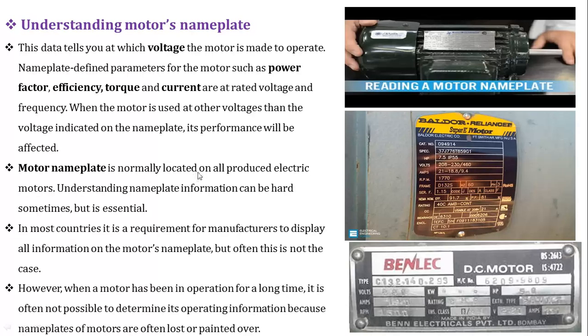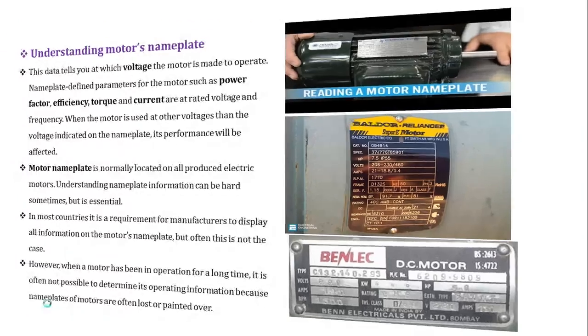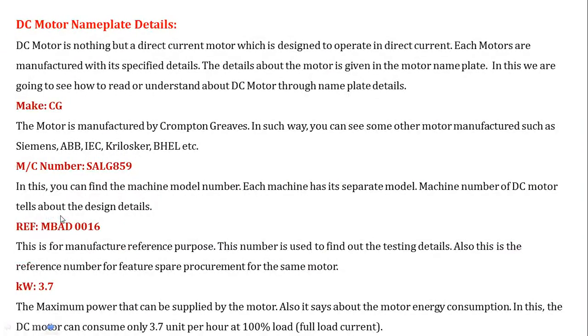The motor nameplate is normally located on all produced electrical motors. Understanding the nameplate's information can be hard sometimes, but it is essential. In most countries, it is required for the manufacturer to display all the information on the motor's nameplate, but often this does not happen. Also, when the motor has been in operation for a long time, it is often not possible to determine its operating information because the nameplates are often lost or painted over. This may happen for some reasons.